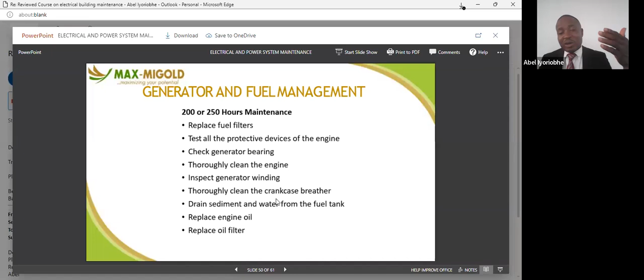So you have to pay adequate attention. At 500 hours, this is what we do: we inspect the radiator cap. That radiator cap can also put you in trouble, giving a false alarm when it's vaporized, and shutting down the generator as the sensor senses it. You go there, you check it, uncheck it, and the generator goes back on. So you check all the little things.